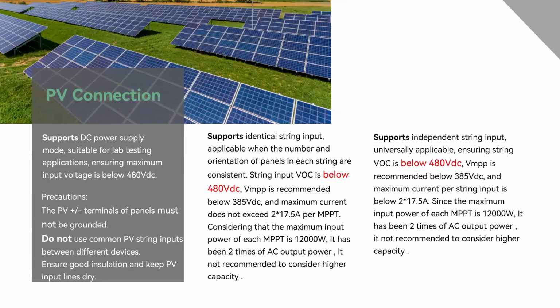And now let's move on to the PV connection. Firstly, we support a DC power supply mode, which is suitable for lab testing applications. Just ensure the maximum input voltage is below 480 volts DC. And when we install the PV panels, make sure that the terminals of the panels must not be grounded and do not use the common PV string input between different devices. Also ensure good insulation and keep PV input lines dry.